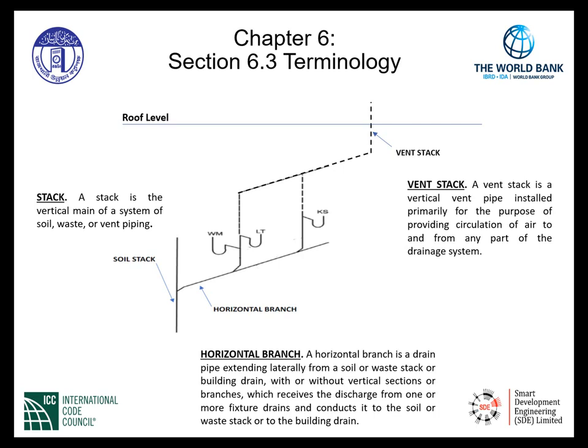A 'vent stack' is a vertical vent pipe installed primarily for the purpose of providing circulation of air to and from any part of the drainage system. In the drawing, the vent stack is completely piped through the roof level of the building, allowing atmospheric air to be introduced into the piping system through this connection into the venting system of our sanitary drainage system.